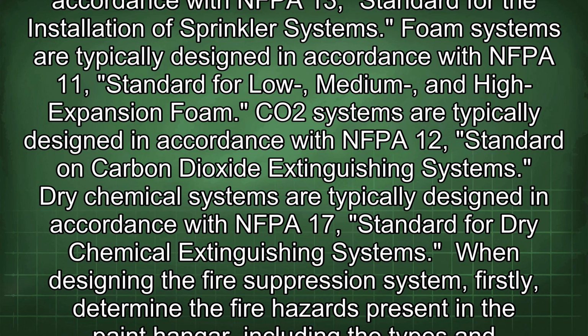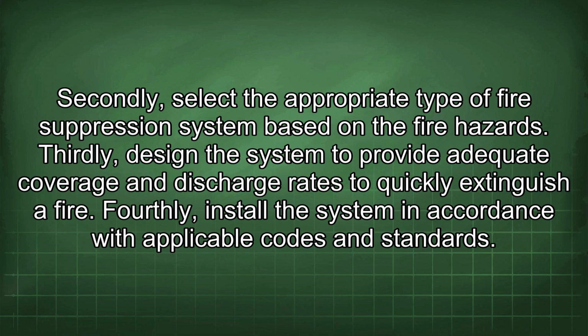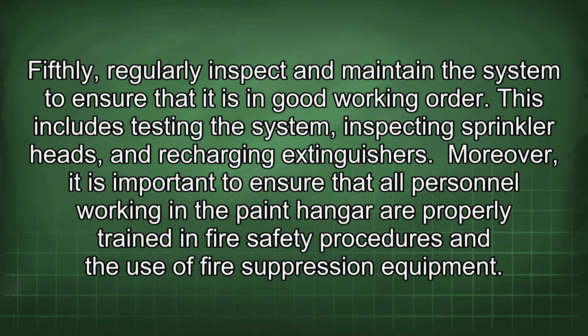When designing the fire suppression system, firstly, determine the fire hazards present in the paint hangar, including the types and quantities of flammable materials. Secondly, select the appropriate type of fire suppression system based on the fire hazards. Thirdly, design the system to provide adequate coverage and discharge rates to quickly extinguish a fire. Fourthly, install the system in accordance with applicable codes and standards. Fifthly, regularly inspect and maintain the system to ensure that it is in good working order. This includes testing the system, inspecting sprinkler heads, and recharging extinguishers.